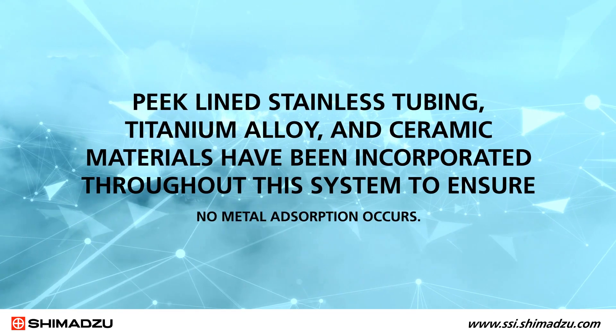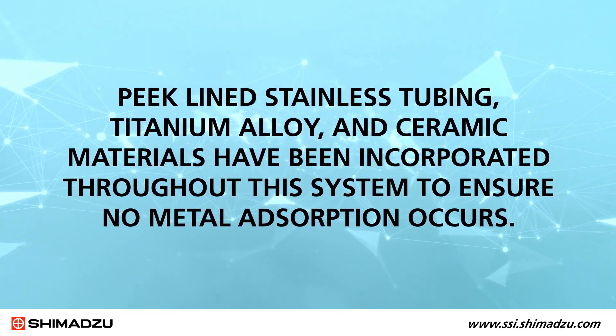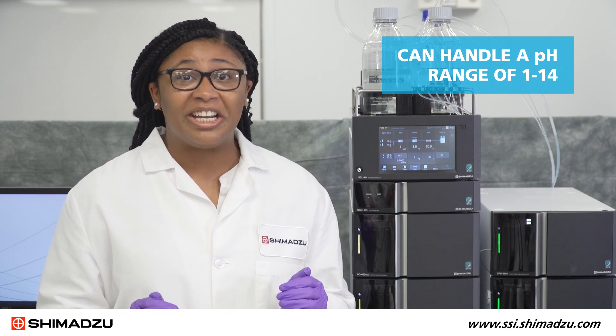PEEK lined stainless tubing, titanium alloy, and ceramic materials have been incorporated throughout this system to ensure no metal adsorption occurs. Additionally, it also provides corrosion resistance from mobile phases using high concentrations of salts and halogens. The system has a maximum pressure of 15,000 psi and can handle a pH range of 1 to 14.